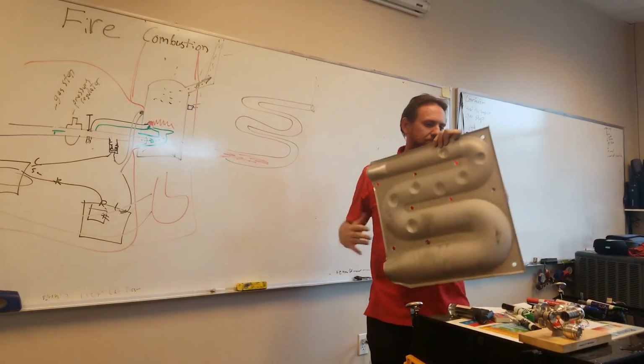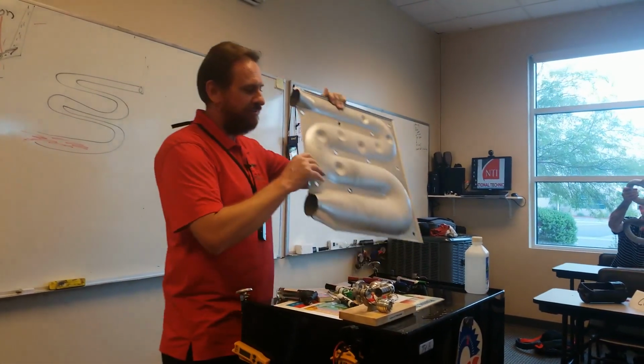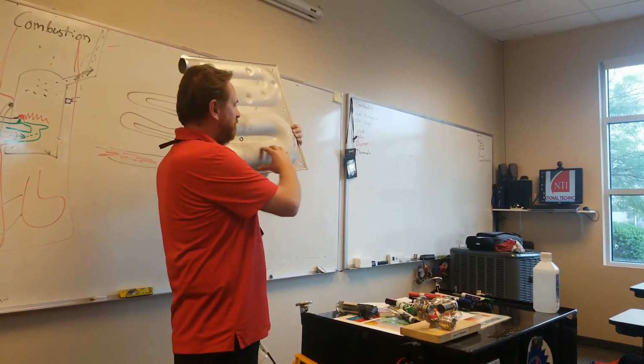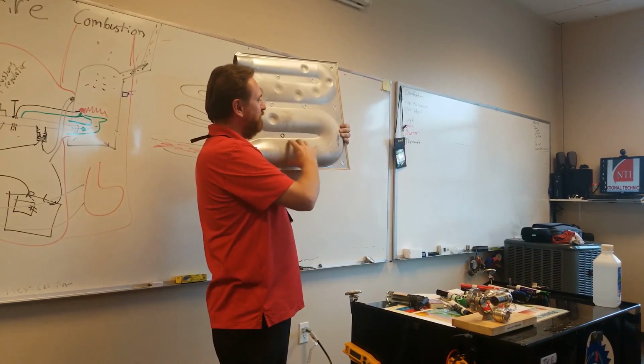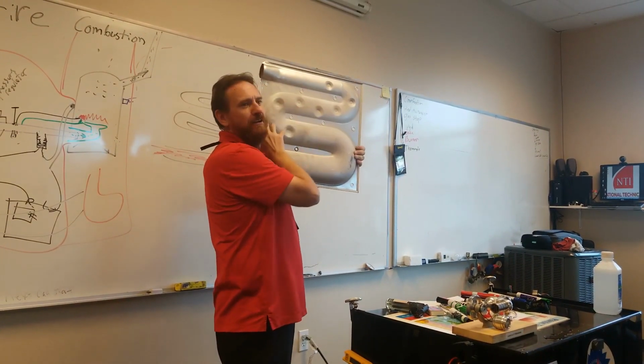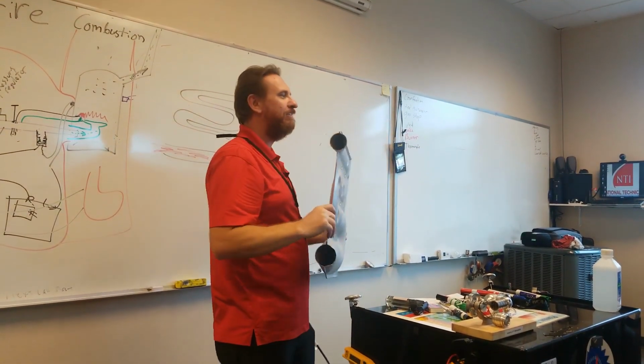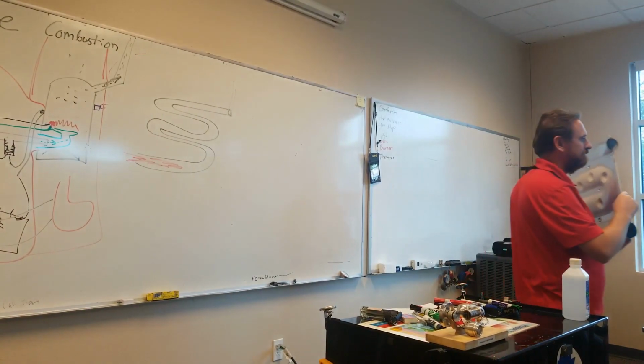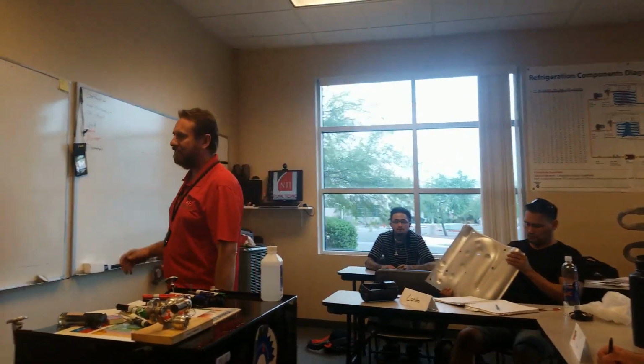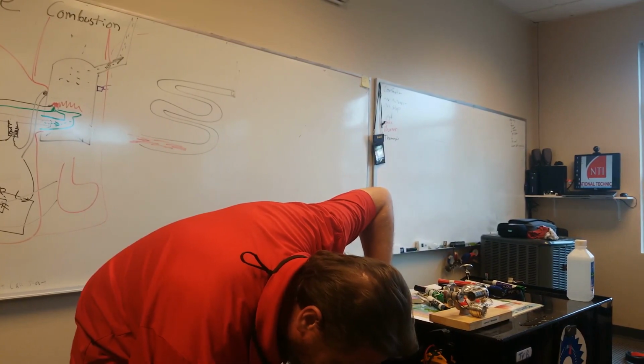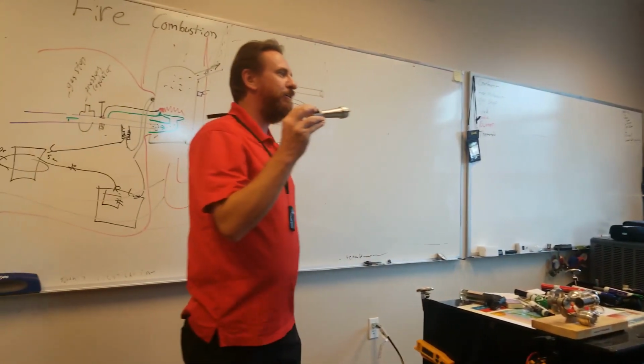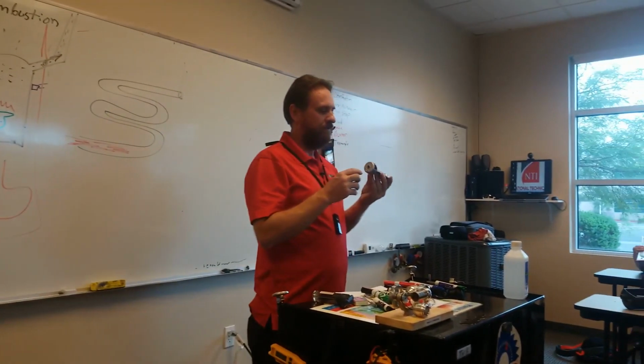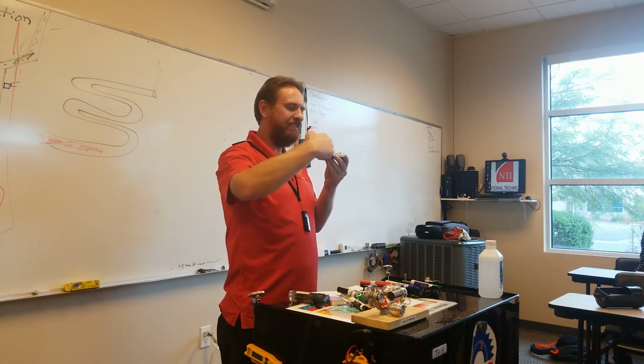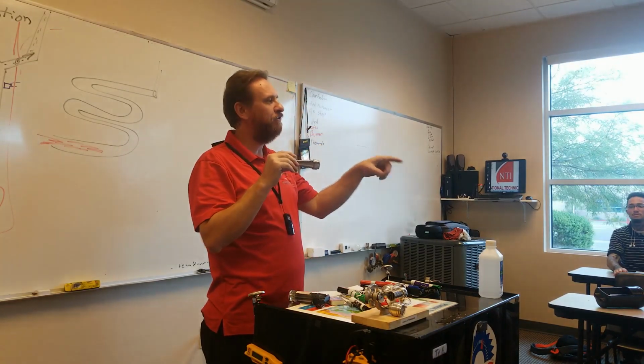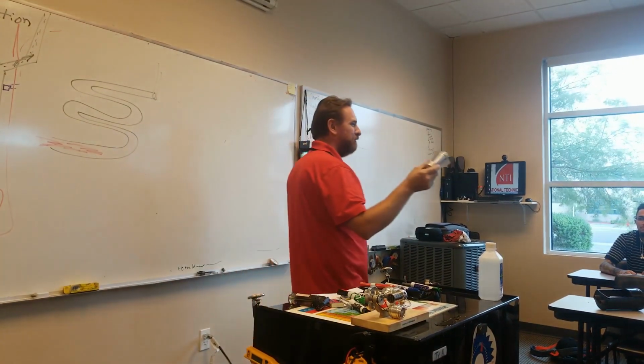Here's another style. On this style, we have the fire burning in this first tube. Then it's just the hot gases pulling. But notice they took this tube and made it smaller, and they put these little divots in there so they can increase heat transfer. It's another style of heat exchanger. I could have 3 or 4 or 2 or 1 of these. To make the fire burn at an angle, we need a special type of burner. We need a burner like this. We call it a jet burner or an in-shot burner. The spud fits here. It mixes the air, comes in the side, and shoots it across, and then the inducer draft pulls it the rest of the way through. These are the burners we're going to be using.